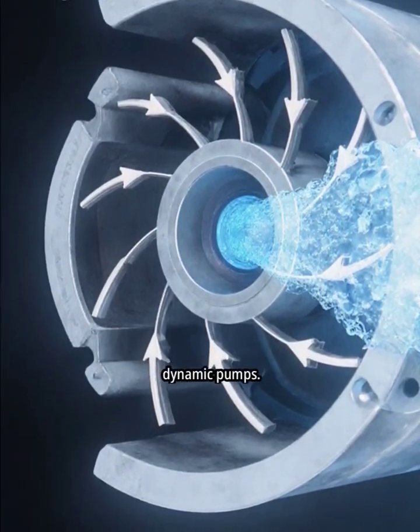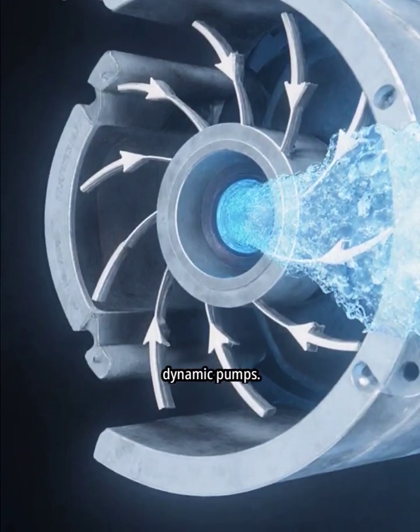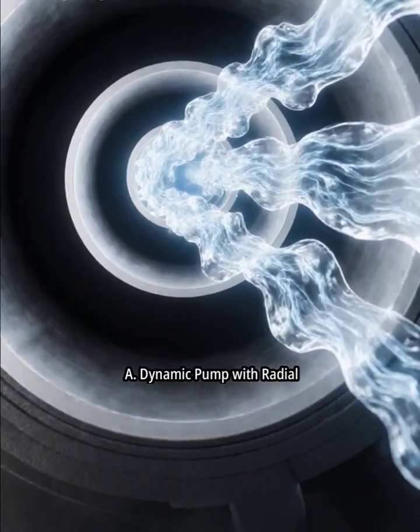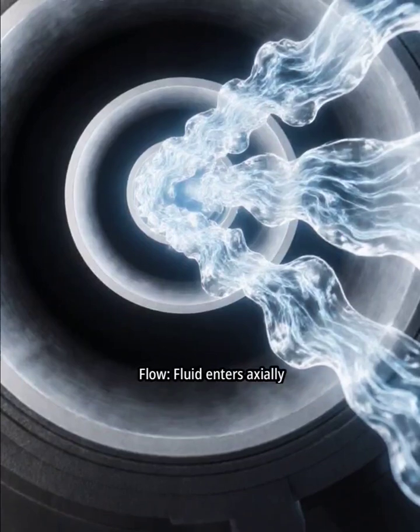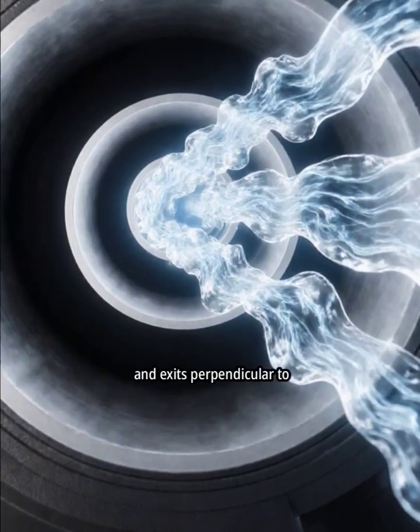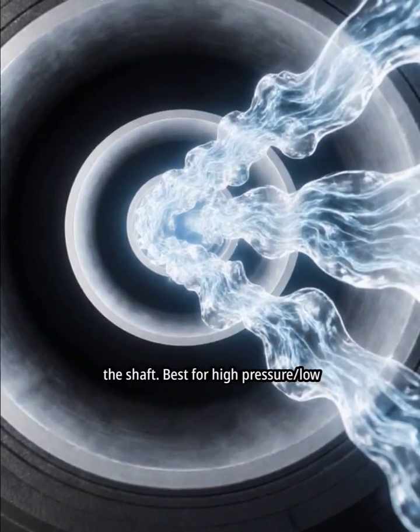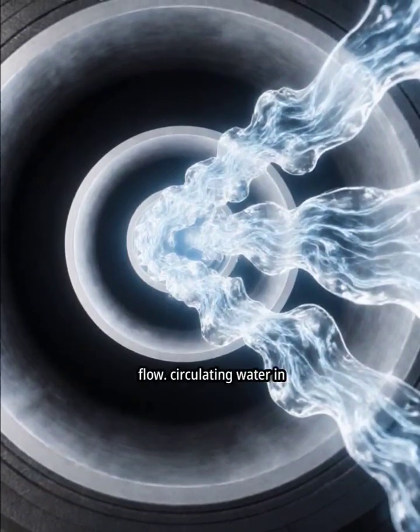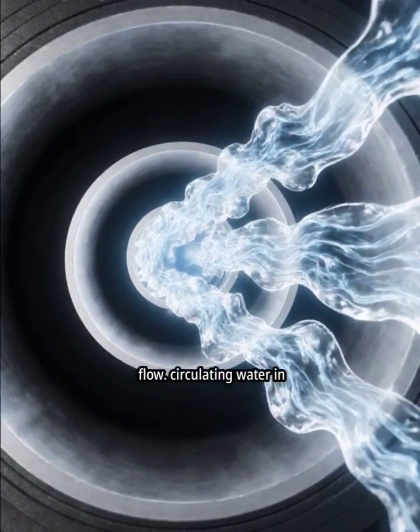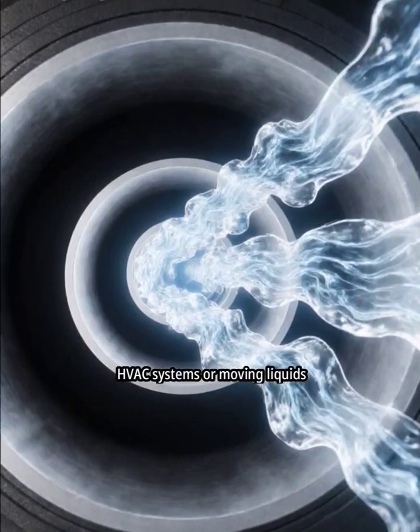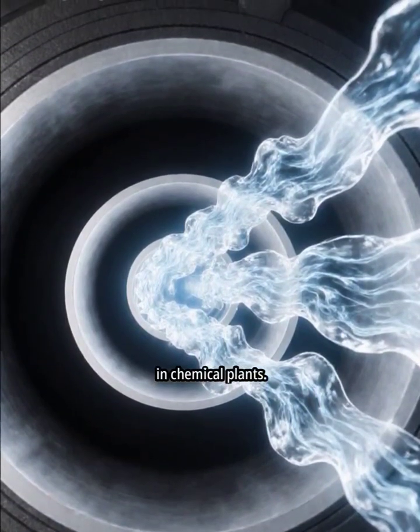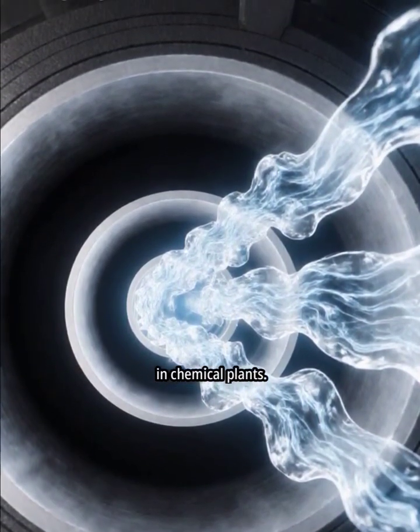Dynamic pumps are further subclassified. A. Dynamic pump with radial flow. Fluid enters axially and exits perpendicular to the shaft. Best for high pressure, low flow. Used for circulating water in HVAC systems or moving liquids in chemical plants.